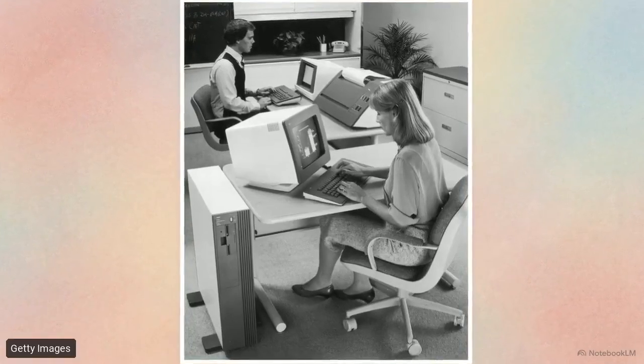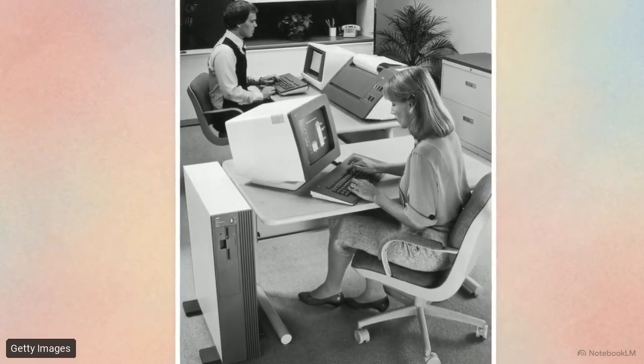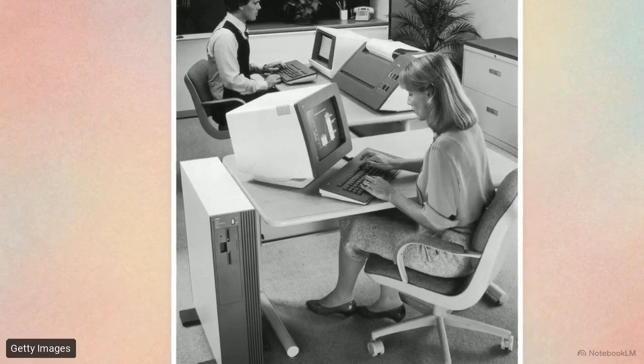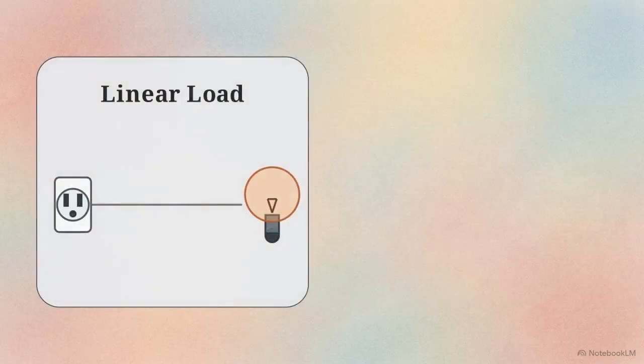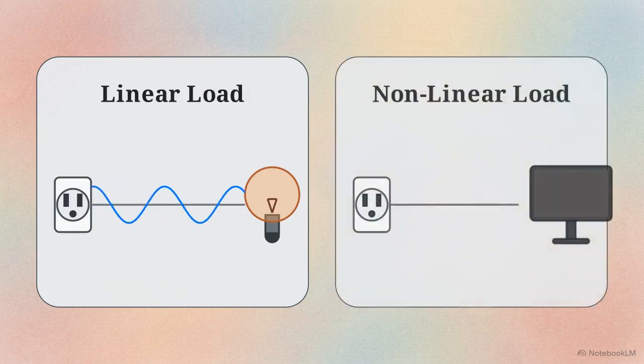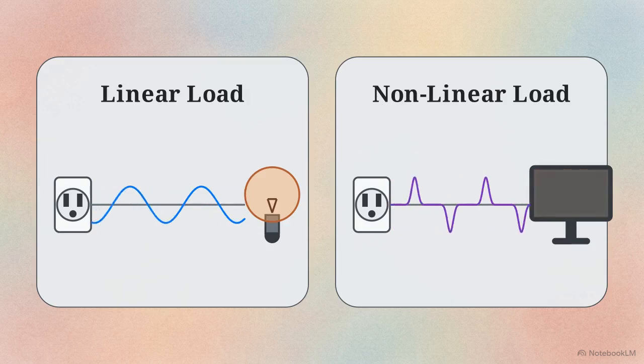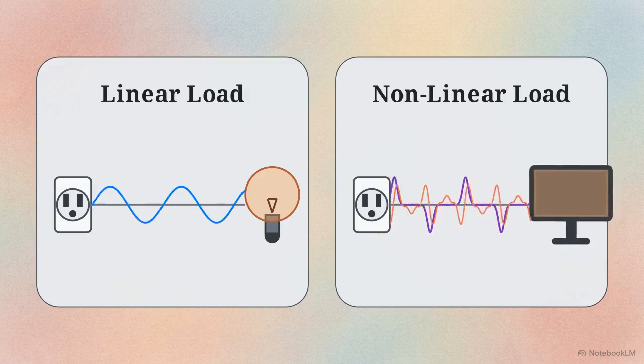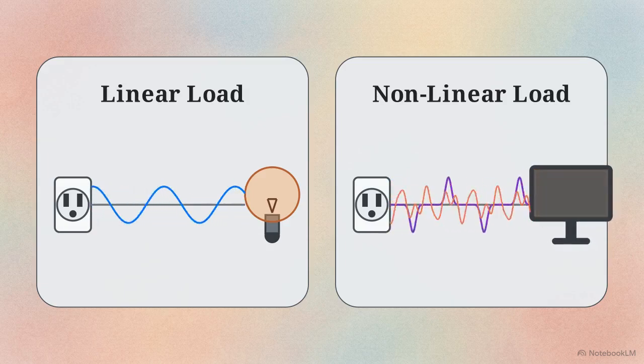Look at the early computer workstations that flooded offices in the 80s and 90s. These devices broke that perfect balance. Unlike a traditional light bulb or industrial motor, modern electronics don't draw power in a smooth, continuous flow. They gulp it in abrupt, distorted pulses, injecting a massive amount of electrical noise backward into the building's wiring.